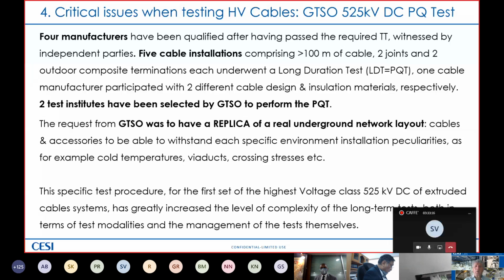The request of the German TSO was to have a replica of a real underground network layout. So they wanted cable and accessories able to withstand each specific environmental installation peculiarity, like cold temperature, since we are outside and we are in Germany, cold viaducts, crossing stresses, tunnels, and so on. And for the first time, of course, we tested the highest voltage class of 525 kV DC of extruded cable system. Together with the real underground situation, this increased the level of complexity of the long duration test in terms of test modalities and management of the tests themselves.